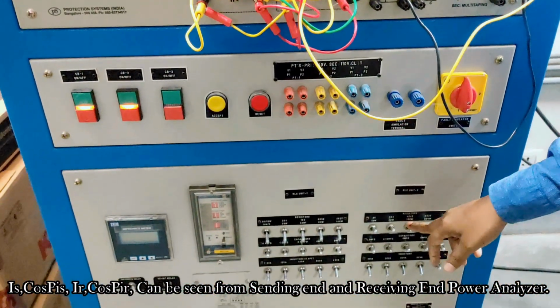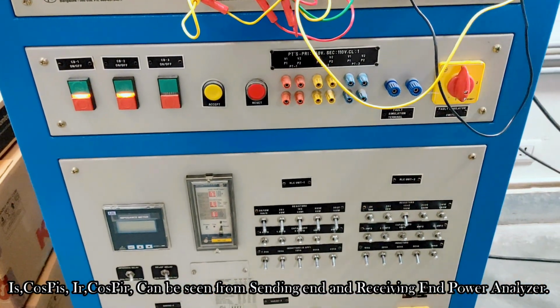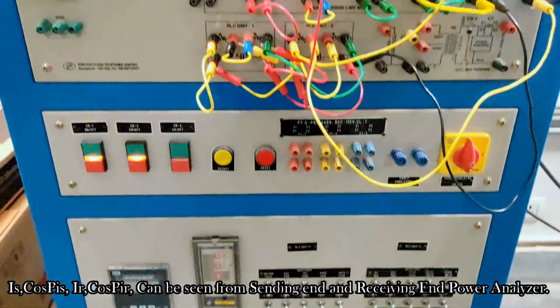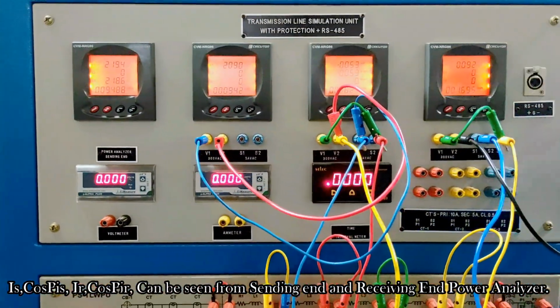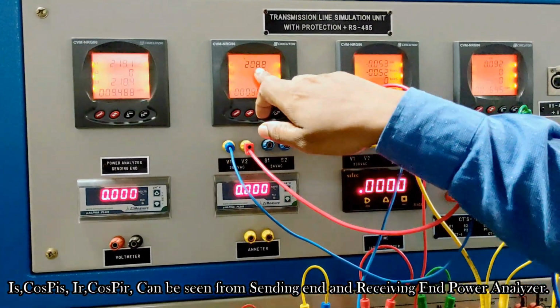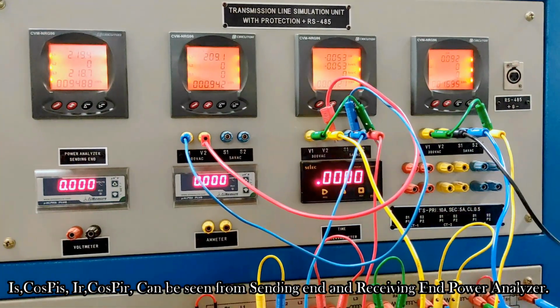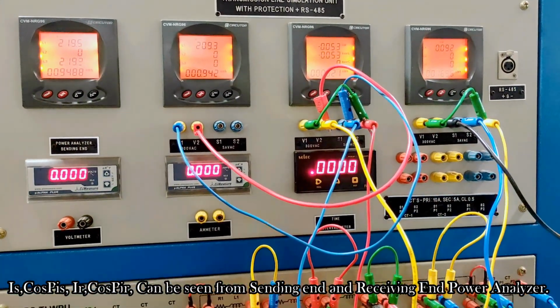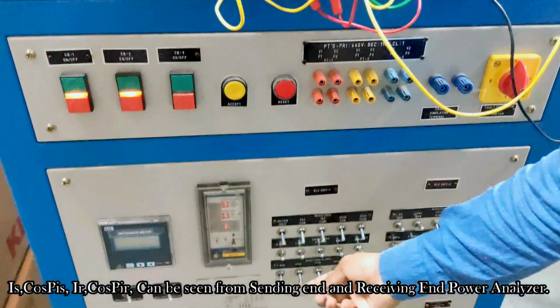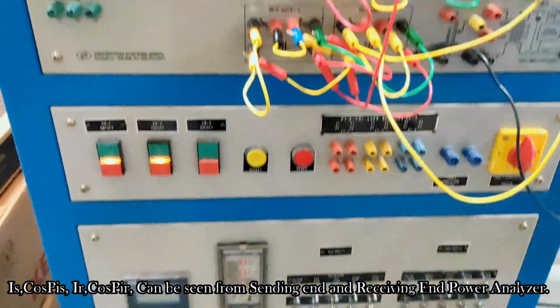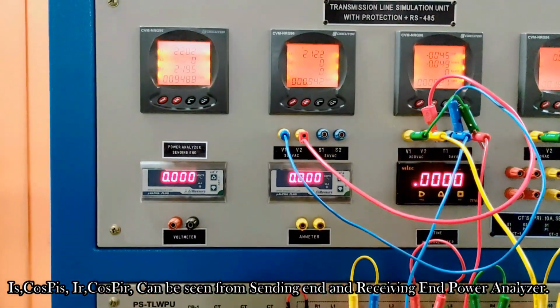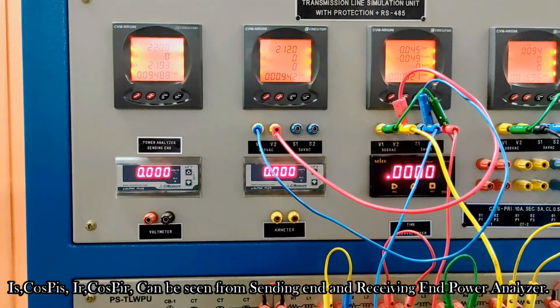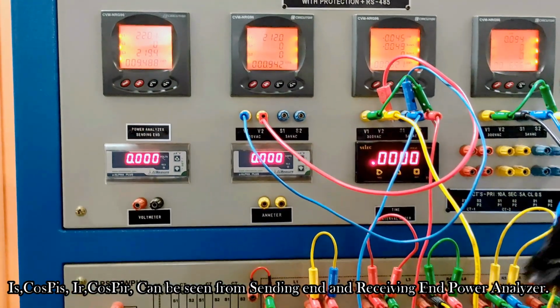So now we will connect the 100 watt load. I have connected the 100 watt load. As you can see, it is showing near around 100, and the voltage is reduced to 209. So again we have to reduce the L compensation. Our voltage increased to 212. Again this, that is 212.